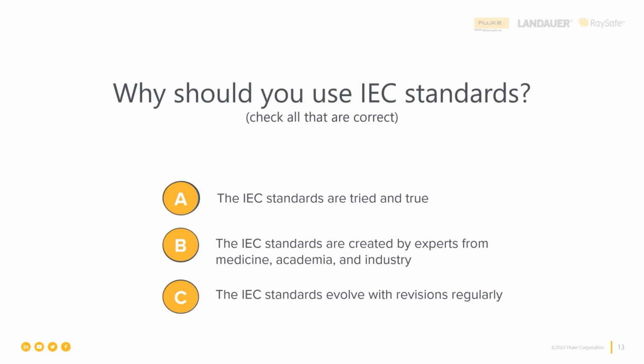And I should acknowledge that some countries produce their own local national standards that use the IEC standards, but then maybe make them a little bit tighter in terms of pass-fail criteria or things like that. China is one of those countries that do that. Australia and New Zealand are countries that also have their own local national standards, but they track very well and have the same or very similar requirements as the IEC standards have. And therefore, they are always a good place to start.